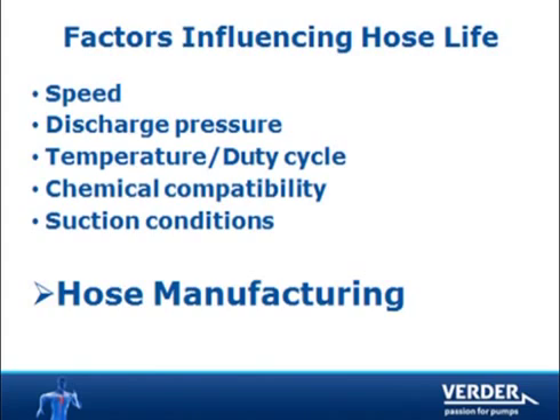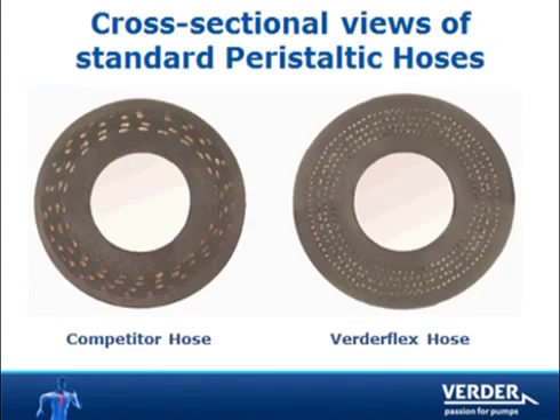It is our proprietary manufacturing process that makes our hose the market leader. As you can see, the Verderflex hose has many more nylon reinforcement fibers than our competition. These nylon layers absorb the compression load as the pump rotor turns — twice per revolution the rotor shoes compress the hose, exerting great force. This force is absorbed by the nylon fibers.